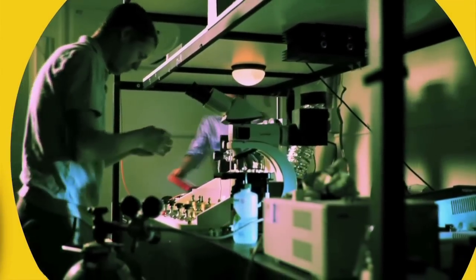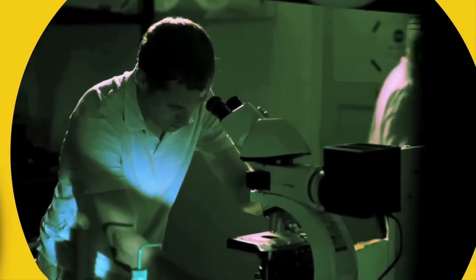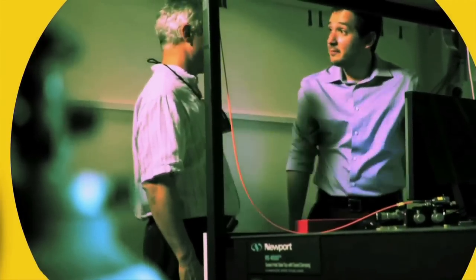The way the dosimeter works is that the material itself accumulates information about the radiation, which you can then read out using light. You can choose whether you read it out instantaneously in real time or let it accumulate to give you a picture over a longer time period.